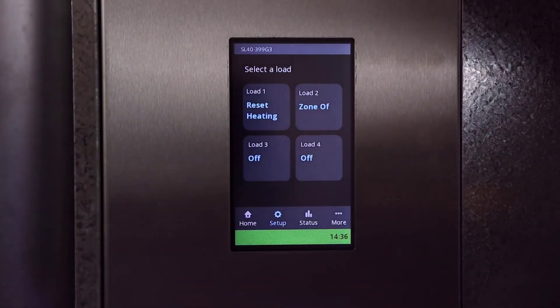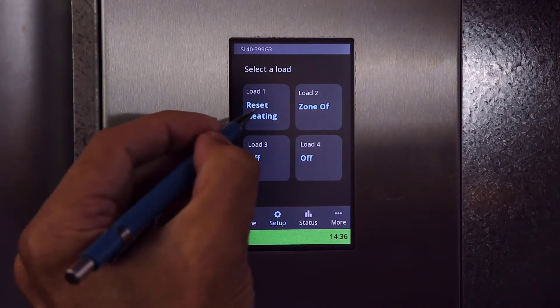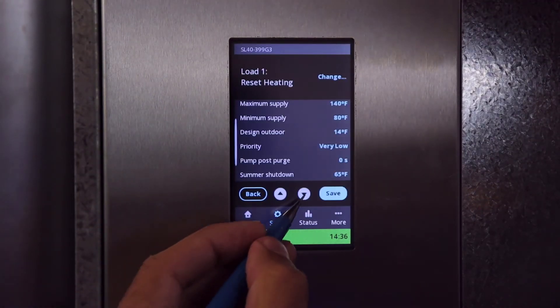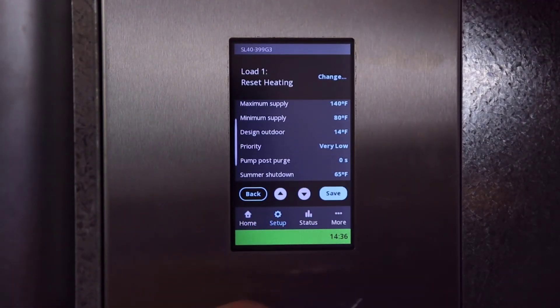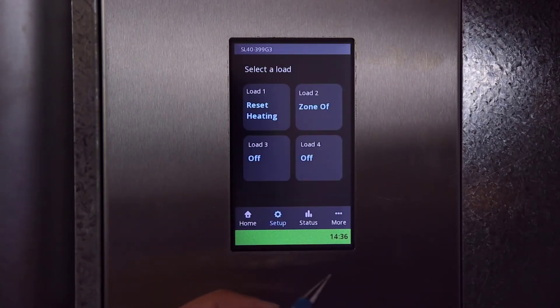Let's start with Setup. Here you can see four different loads. This is the go-to menu to enable and edit loads on a new installation. If you wish to run multiple pumps at the same time, you'll set up a load and link others by defining them as zones. One thing that's different on this new version is these up and down arrows — previously you had only the sidebar for scrolling, but these new arrows are easier for fingers. The Setup tab will have the settings necessary for most installations.